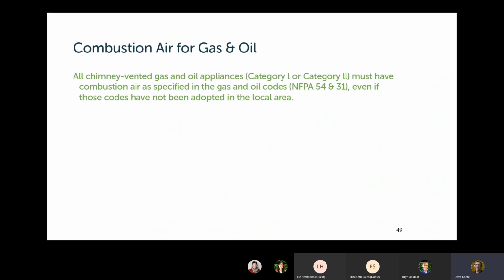And another requirement is that there has to be combustion air for any gas or oil appliances vented into chimneys. There is a little confusion about this because in most of Vermont, the gas and oil codes have not been formally adopted. So chances are where you live, there's no oil code. And chances are where you live, if you're not on Vermont Gas's system, there's no enforced gas code either. And those are the codes that we look to for details on how to provide combustion air. So it's a little confusing, but the Vermont code requires that combustion air be provided. It requires that it be provided as specified in the national gas and oil codes, even if those codes have not been adopted in the local area.